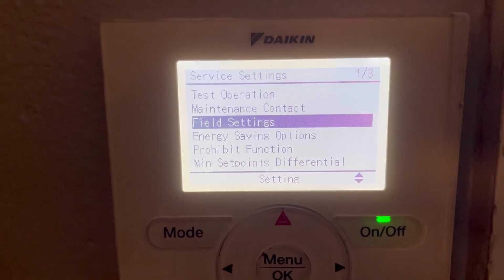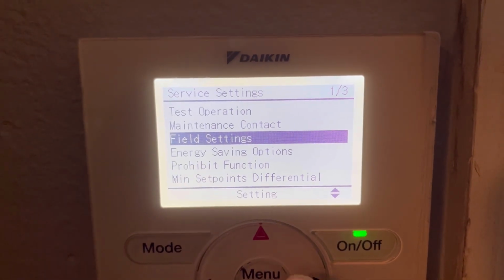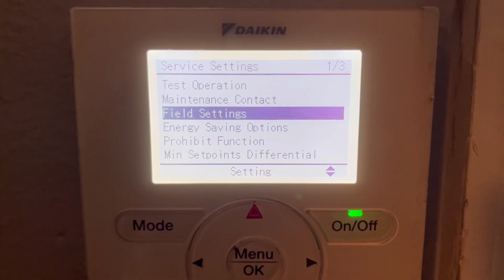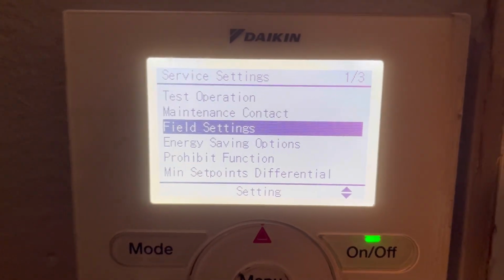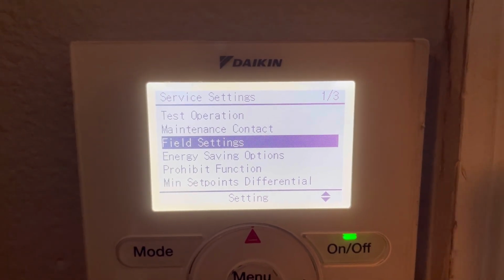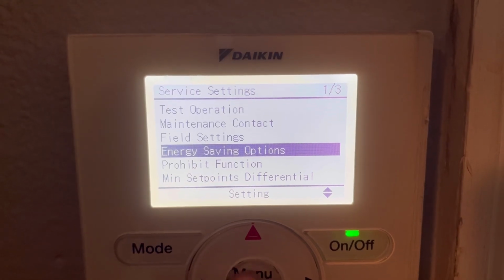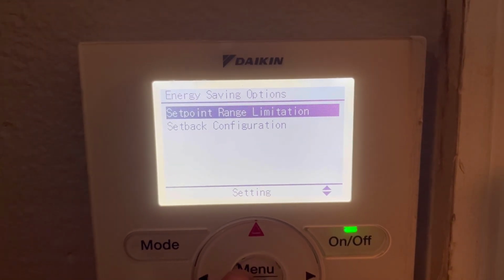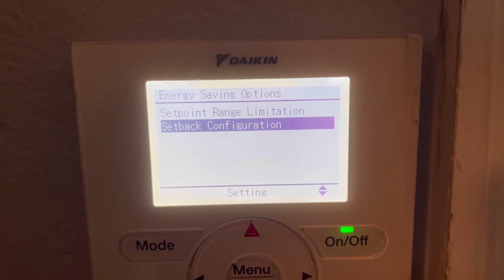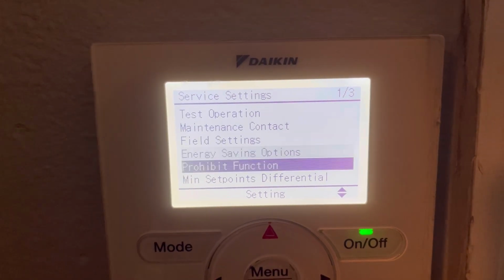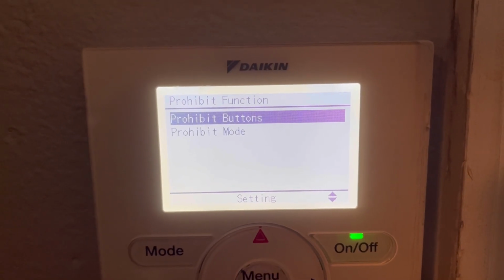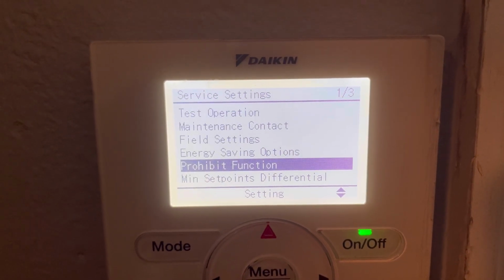That's where you change things like what fan speed it runs at whenever it satisfies in cooling or heating, or if it has a drain alarm, or to turn the drain pump off, or to offset the thermostat. Energy savings options. This is where you would come to lock out specific controls like set point range limitations, setback configuration. Prohibited functions. Maybe you want to lock out specific buttons or specific modes. You would do that here as well.